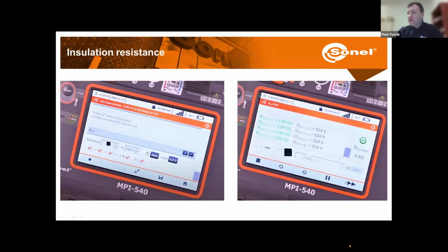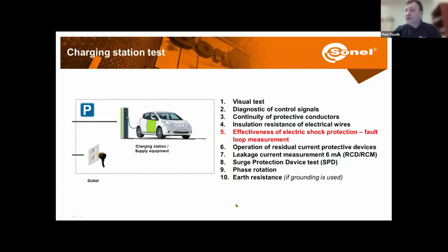So with our meters, depending on which meter you are going to use, you can select what configuration you want to check. So different between lines, line to neutral, line to line. And then the meter will just make all the tests in a sequence and give us the overall result at the end. So that's a convenient way.